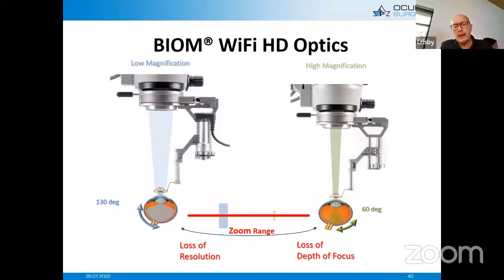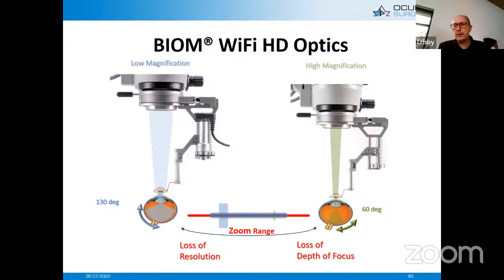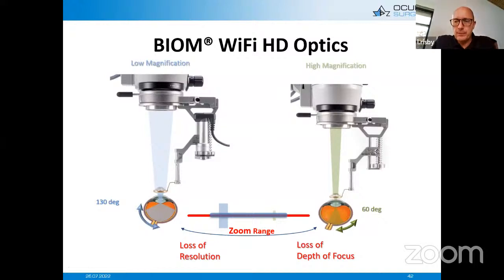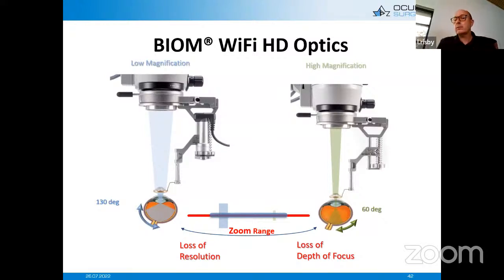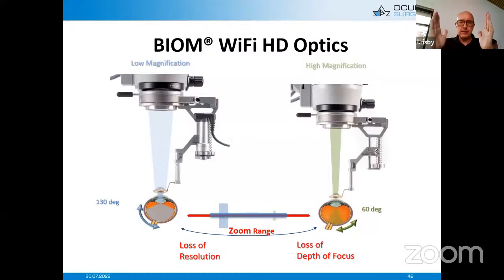What I have found out — and I call this the sweet range — the low point is about 7x magnification (it can be a little less or more). The other end is about 16–17x. With the Oculus optics, you should get enough magnification to see the macula and do your surgery at around 17x. My recommendation is to stay in between 7 and 17.